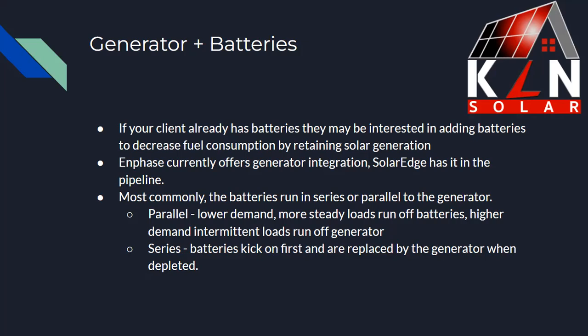Enphase currently offers generator integration. SolarEdge has it coming soon. But most commonly, and what you've seen most in the past and currently, is that batteries are either going to run in series or parallel to the generator. When you run them in parallel, you basically put your low demand, more steady loads on the battery, and your high demand intermittent loads on the generator, so that the generator can kick on or off, or rev up or down, depending how it's set up.